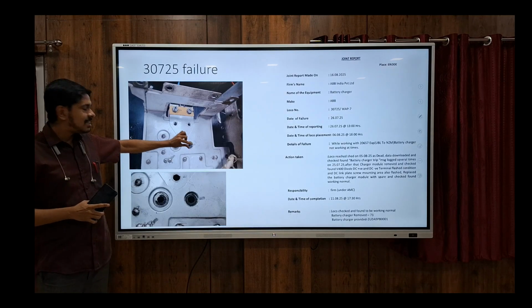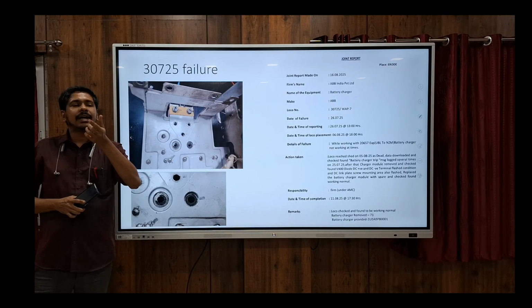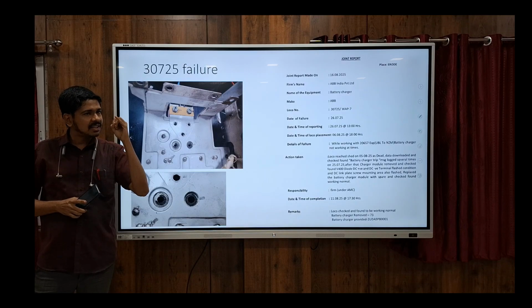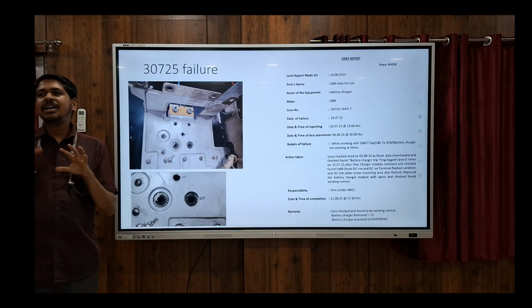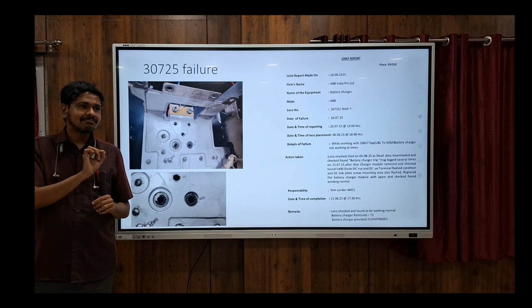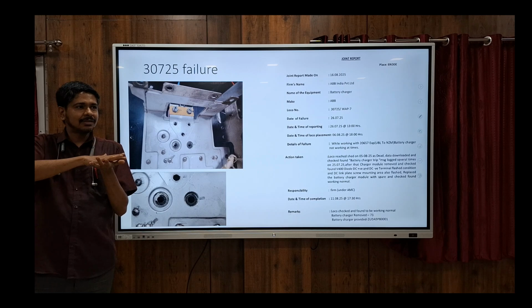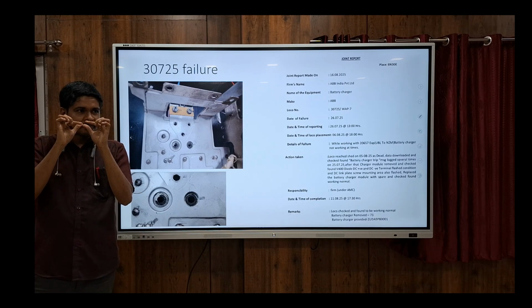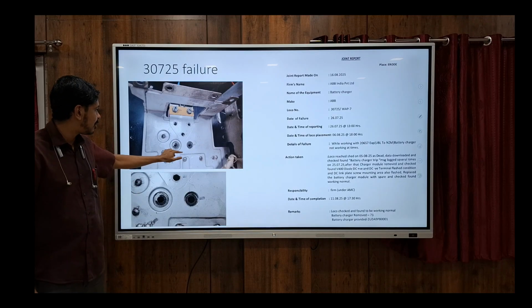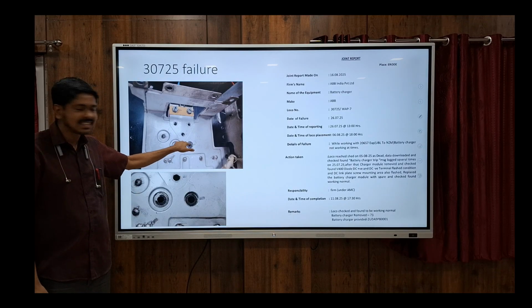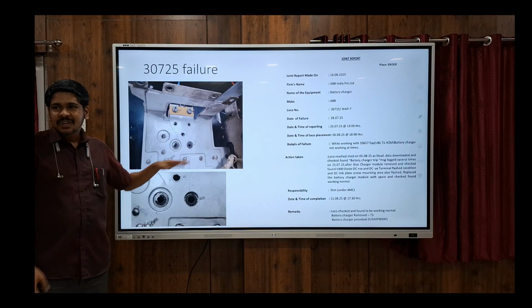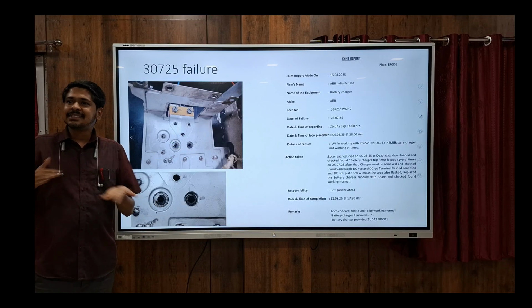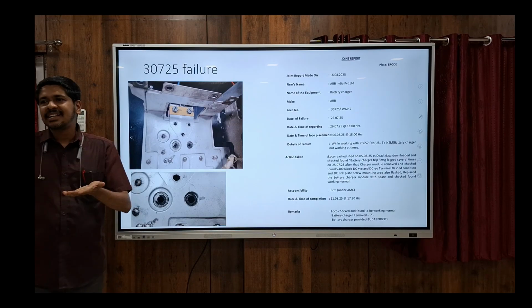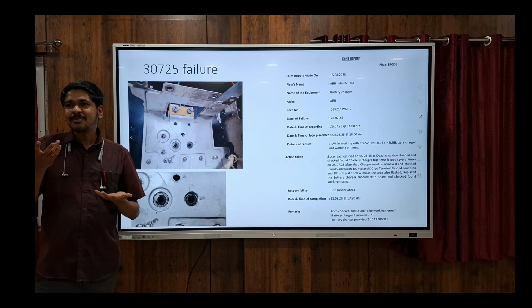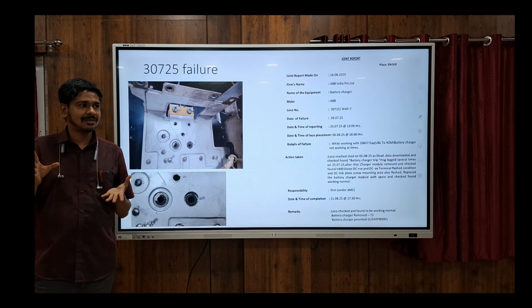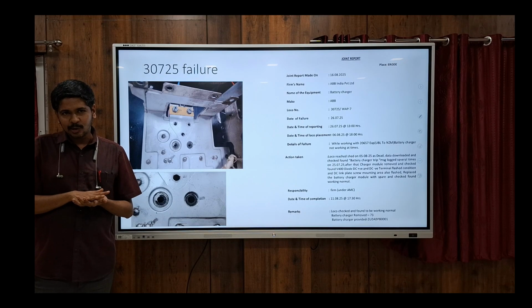In the tightening, when we change the IGBT, there is a spring washer and a flat washer used. What happens with the spring washer is, once it is used and then taken out and reconnected, its spring property is lost, and this has finally created a flashover between the positive and negative plates inside. This positive-negative flash means the DC link is shorted. So sometimes the battery charger will work when the DC link is built up, otherwise it will not work. This resulted in the failure.